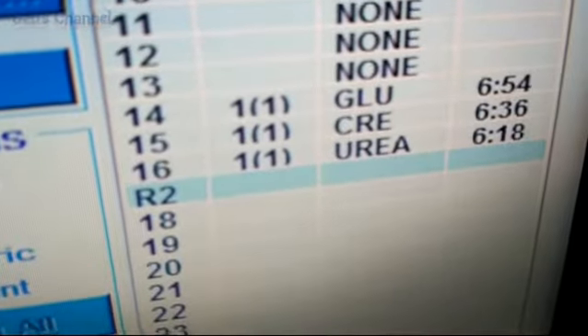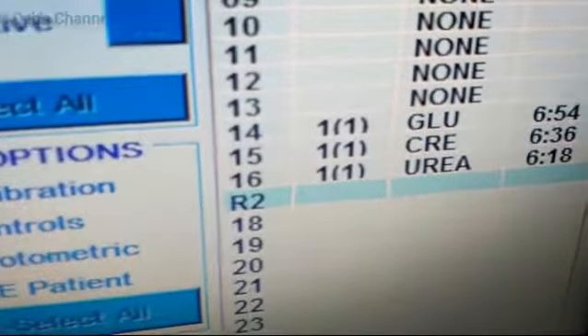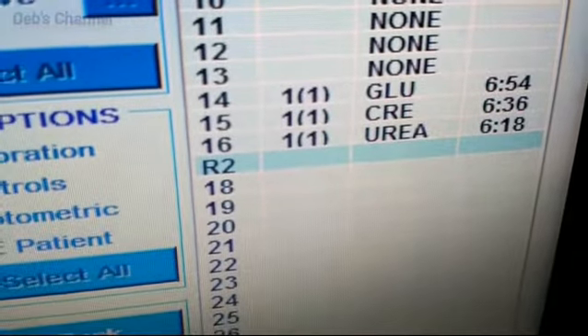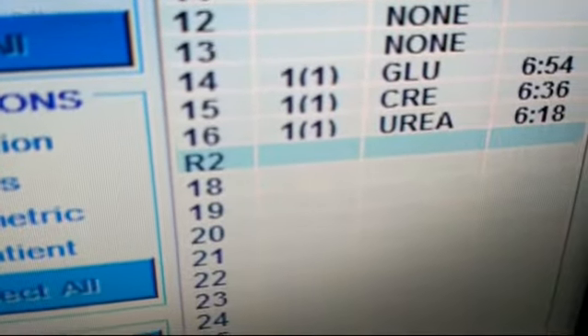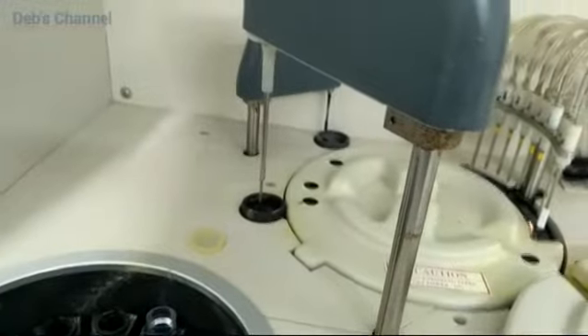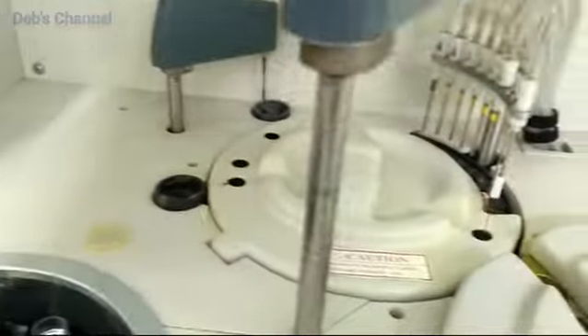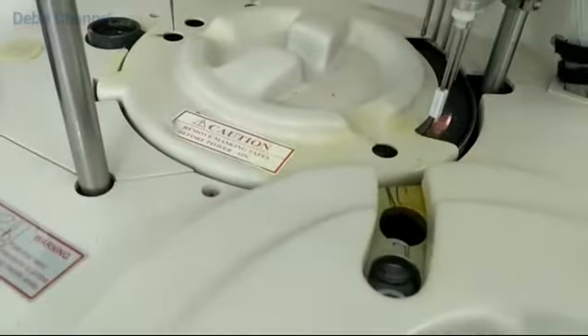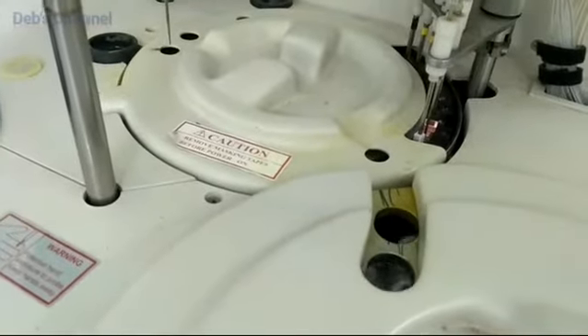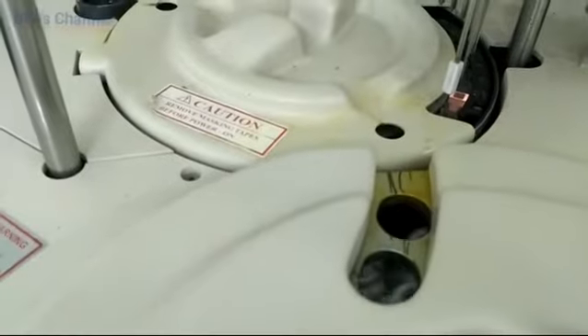Okay, the test is going on for taking reagent 2. Glucose is a single reagent, but urea and creatinine will be double reagent. So now this is the time for taking the urea reagent. Look at the machine. The probe is going for taking the reagent for urea. Look, the probe is taking the reagent and the mixer is mixing. Okay, now the probe will take the reagent for creatinine. The probe is taking the reagent and putting it in the cuvette, and the mixing.